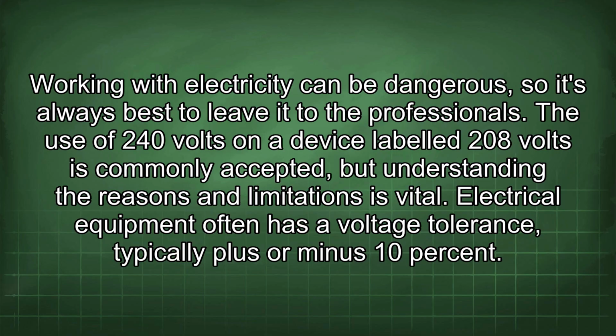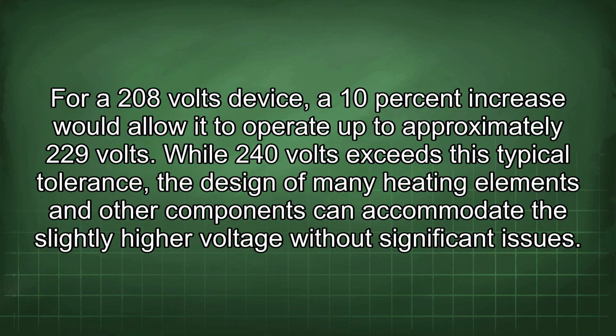The use of 240 volts on a device labeled 208 volts is commonly accepted, but understanding the reasons and limitations is vital. Electrical equipment often has a voltage tolerance, typically plus or minus 10%. For a 208 volts device, a 10% increase would allow it to operate up to approximately 229 volts. While 240 volts exceeds this typical tolerance, the design of many heating elements and other components can accommodate the slightly higher voltage without significant issues.